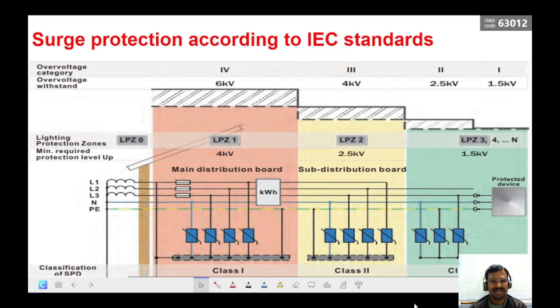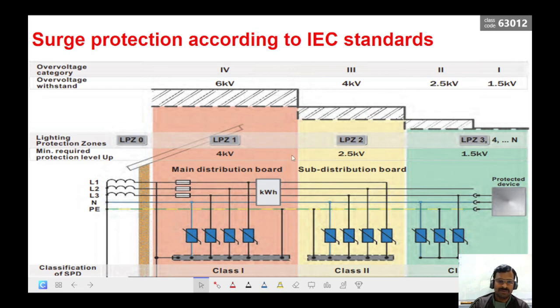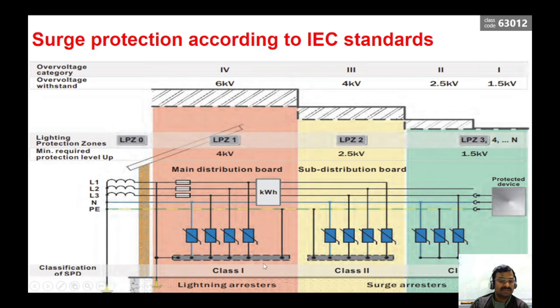What are the different classifications given by the IEC? IEC classifies the zones as main distribution board, sub-distribution board, and near to the load. Based on this, we are going to have the minimum required protection voltage levels of 4 kV, 2.5 kV, and 1.5 kV. We also classify these areas as class 1, class 2, and class 3. Class 1 zone is classified as a lightning arrestor, and class 2 and class 3 areas are classified as surge arrestors.